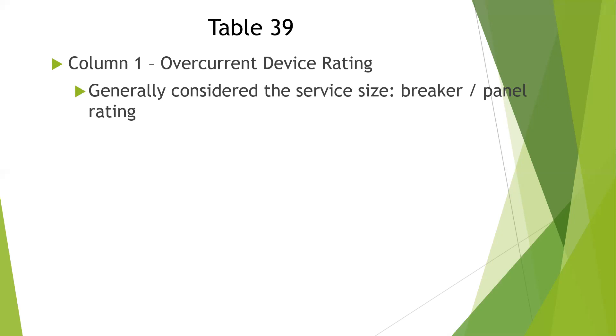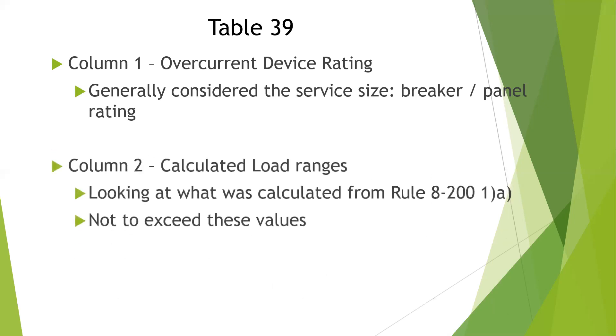Column one is our overcurrent device rating. So if we have 100 amps as what we are looking for, then we go to the 100-amp row. We can use column two to calculate the load for that conductor size. If we look under the 100-amp overcurrent device rating and follow that row for calculated loads of up to 89 amps, just focus on the fact that it's rated for 100 amps.